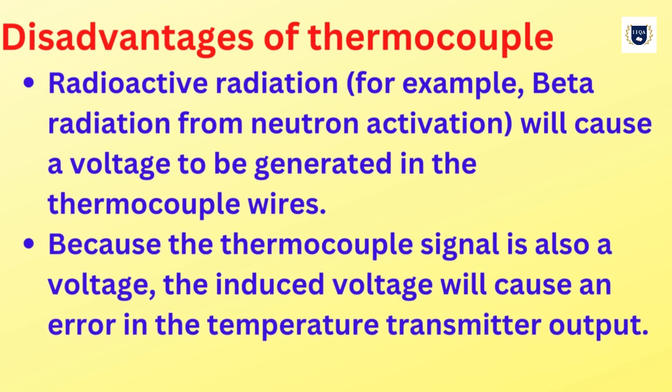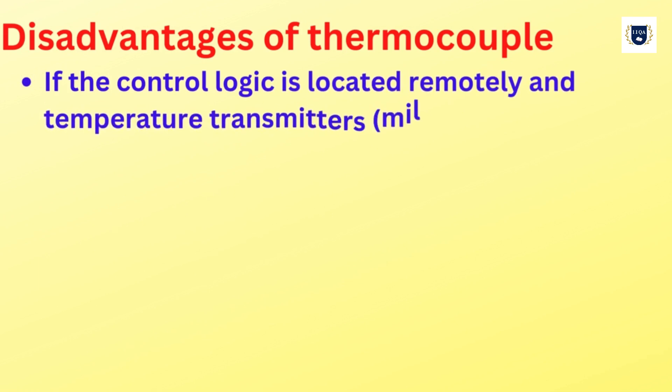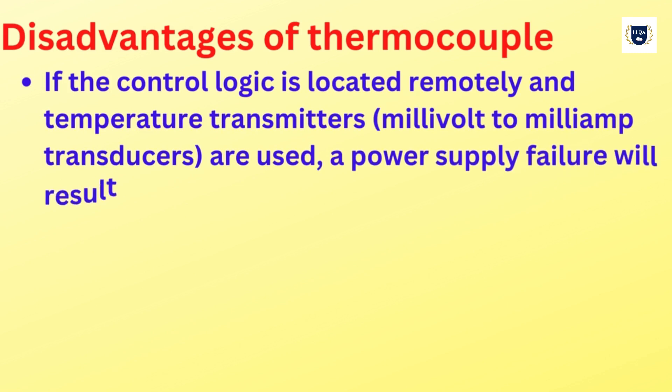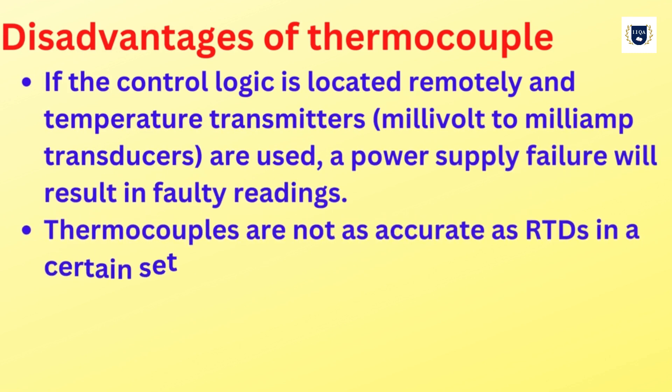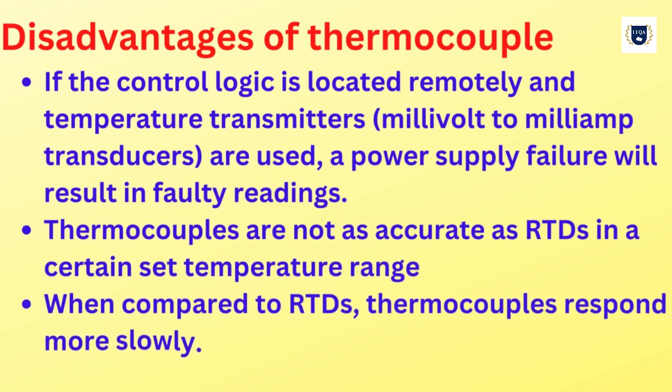Because the thermocouple signal is also a voltage, the induced voltage will cause an error in the temperature transmitter output. If the control logic is located remotely and temperature transmitters — millivolt to milliamp transducers — are used, a power supply failure will result in faulty readings.